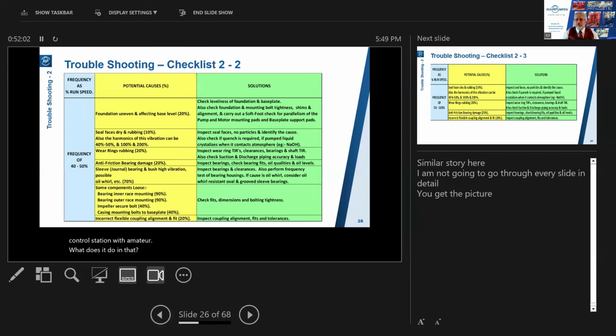Most commonly, the pump vendors do not get involved in these local push button stations. It's most commonly done by the installation contractor. It's part of the on-site wiring. Every time I've seen them specified, nobody quite knows what they want. And all through the phases of supplying the pumps, questions start going back, oh, no, that's not what we meant. Well, you didn't tell us what you meant. What do you want? And nobody really knows. That's why we prefer to keep out of that side.